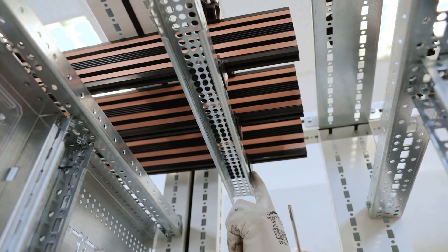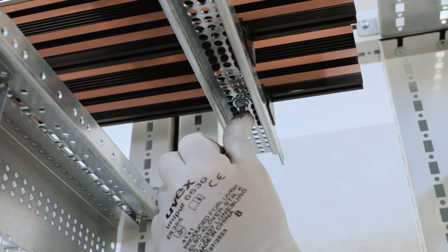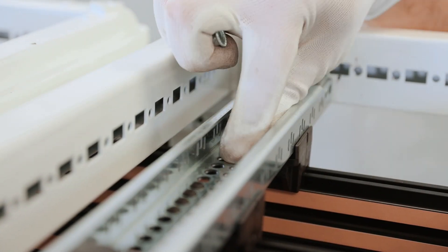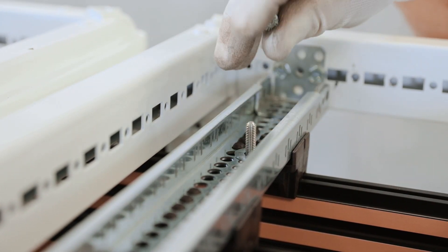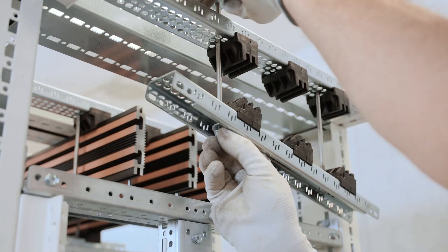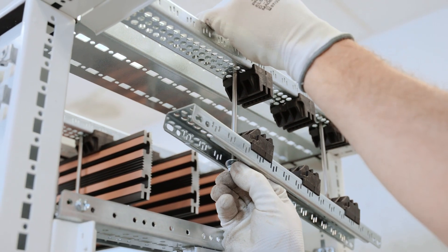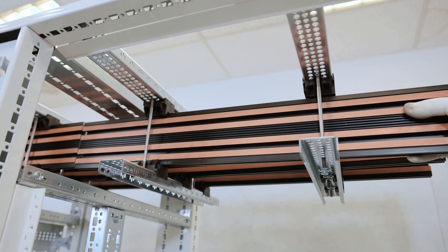Add the threaded rods pre-mounted with a nut and washer. Use one screw per support, put into the holes next to the supports. Fix the upper side with a washer and a nut as well, fixed with a force of 4 newton meters.